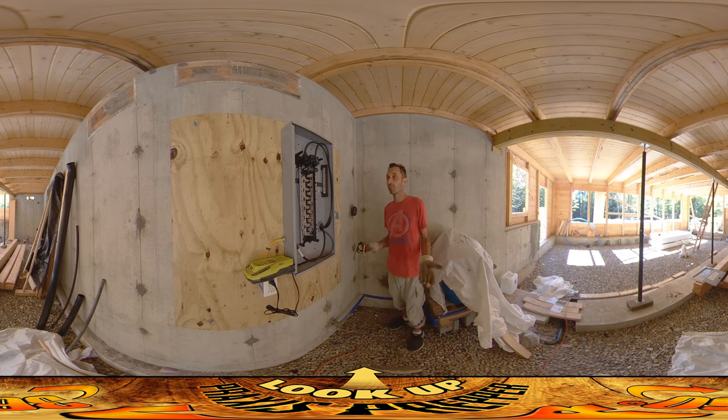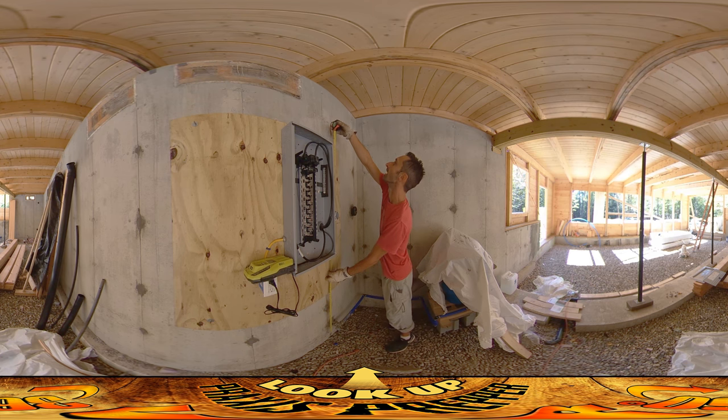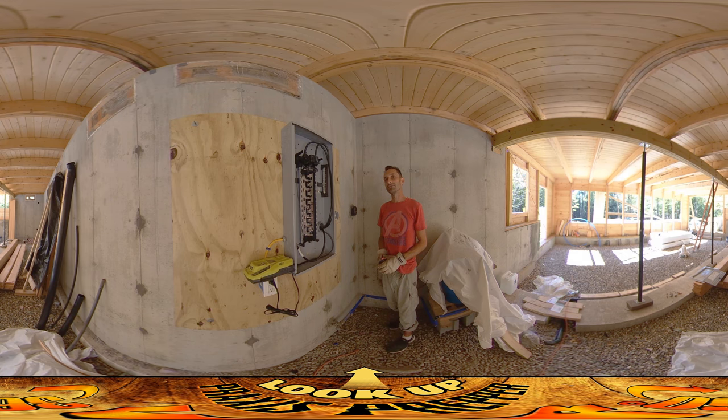He also said it was a foregone conclusion that he couldn't have put the box any higher, because you can't have the shutoff higher than six feet off the floor. The floor line is written right there on the ground, and six feet up is marked right here — so he put the shutoff about a foot lower than he needed to. Everything about this guy is pretty awful.